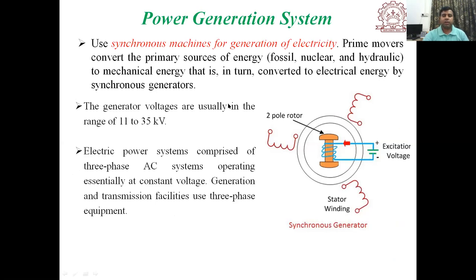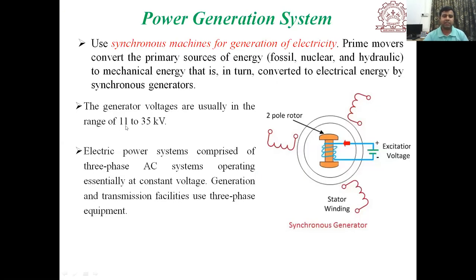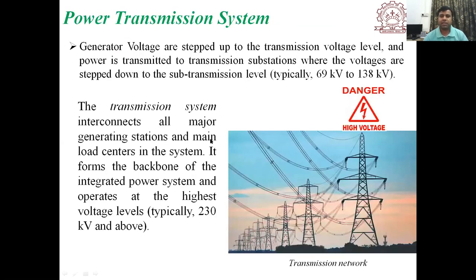The power system overall consists of three main parts: generation, transmission, and distribution. For generation, 60 to 70% of power is generated from thermal power plants. A synchronous machine is used to generate electrical energy from mechanical energy. Generator voltages usually range from 11 to 35 kV. The electrical power system comprises a three-phase AC system operating essentially at constant voltage. The generation voltage is stepped up with the help of a transformer for transmission at reduced losses — transmission is at very high, extra high, or ultra high voltage depending on the power and distance requirements.